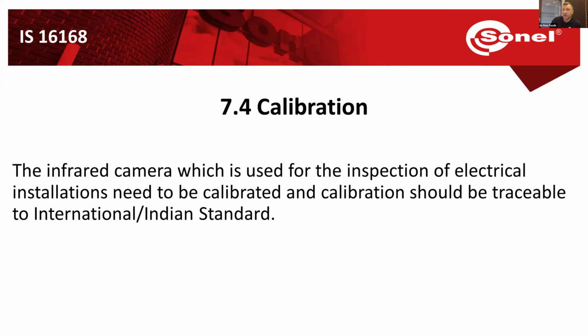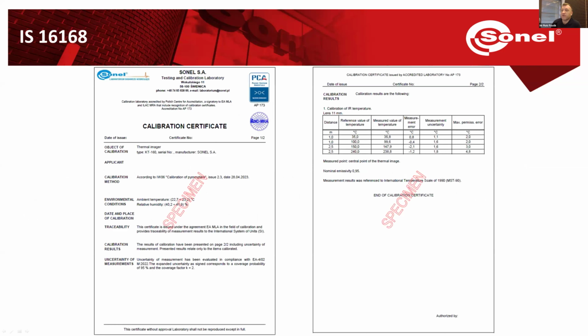Okay, the next thing is the calibration. The infrared camera needs to be calibrated, and the calibration should be traceable to the international Indian standard. The best way to do this is to calibrate your cameras at a laboratory which has NABL accreditation. This is the National Accreditation Board for Testing and Calibration Laboratories. It is the accreditation authority for the laboratories in India, and if the laboratory is accredited, then you will get traceable calibration of your instrument. Now at Sonel, here in Poland, we also have accreditation, also a national body, but different nations, so the name is PCA.